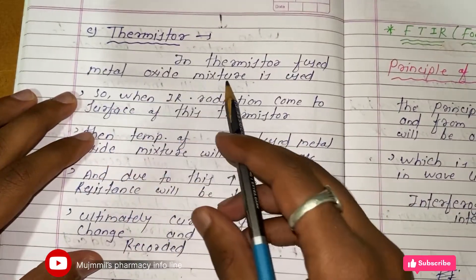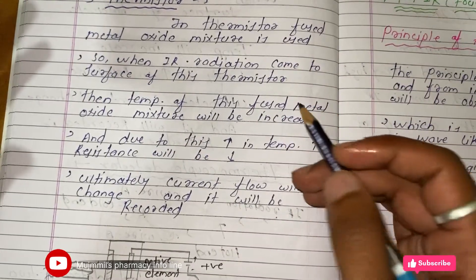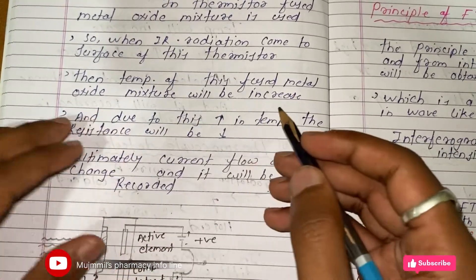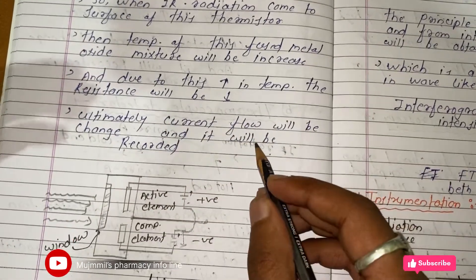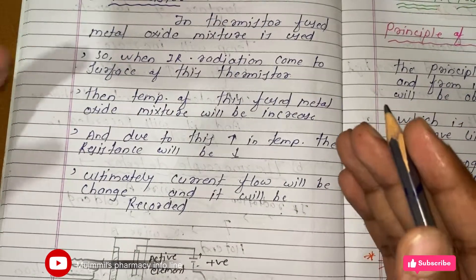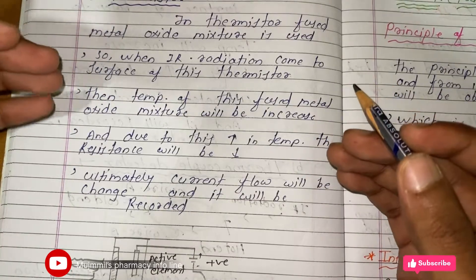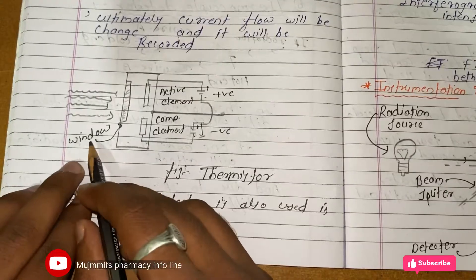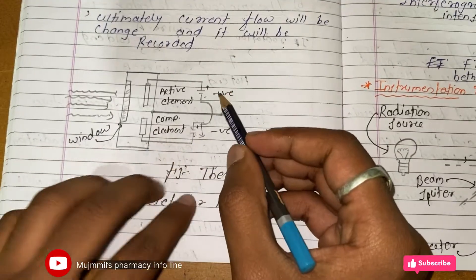The third detector is the thermistor. A fused metal oxide mixture is used. When IR radiation hits the surface of the thermistor, temperature increases, and due to this increase in temperature the resistance decreases, ultimately changing the current flow, which is recorded. The thermistor has a window for IR radiation, an active element, a compensating element, and a current supply connection.